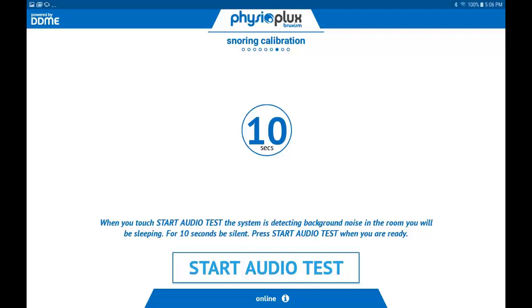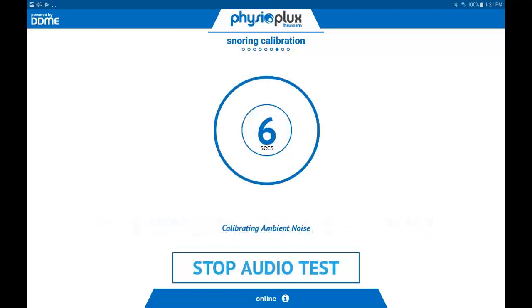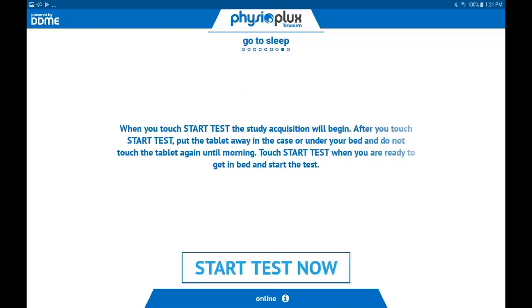Before you press the Start Audio Test, make sure you turn on any fan, radio, or TV that you leave on while you're asleep. This will help clear up any static noise during the test. Now, touch the Start Audio Test button and wait quietly for 10 seconds while the system listens to your room noise level. A timer will count down from 10 to 0. The audio test will measure the background noise that you expect to have while you are sleeping. Once completed, the tablet will automatically advance to the Start Study screen.